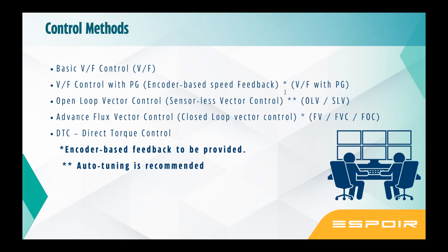Your drive gets a mathematical model of a motor by doing a certain tuning function. In general, in V by F, you feed the motor data. You could be wrong, or you would feed few data which is available on the nameplate. In the open loop method, during auto tuning, you will be able to gauge all the parameters of a motor, not just the kilowatt rating, but what is the load current, what is going to be the line current, what is going to be the iron coefficient, saturation factors.